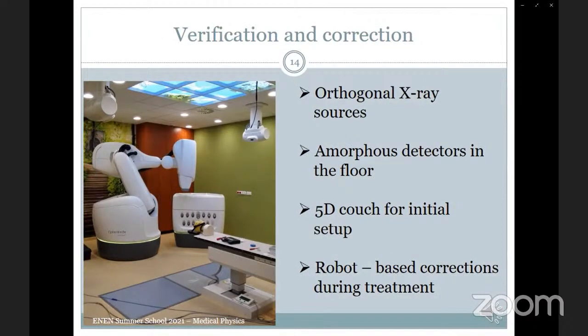How does the verification and correction work on the CyberKnife machine? As I said, we have 2 orthogonal X-ray sources and amorphous detectors in the floor and a 5D couch. During the treatment, we are not moving the couch below the patient, because if you move the couch, the patient can feel the movement and will make sudden movements because of the couch movement. So instead of couch movement, we are moving the robot. So if we measure some patient movement, positioning error, then we send this information to the robot, and the robotic arm will put the source and the beam into the correct position immediately.